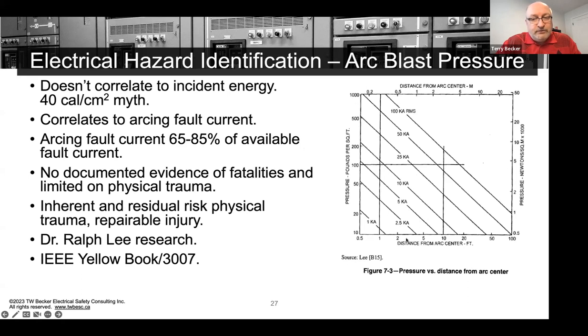This is a graph. We've got distance to the abnormal arcing fault, the arcing fault current, which will be lower than short circuit current, and then the theoretical pressure in pounds per square foot. So just a quick note on arc blast pressure. The good thing is we've now started to add content to 70E and Z462 so the user understands that blast pressure is not what it was previously communicated to be. It is not typically going to be very significant on standard low voltage power distribution and branch circuit electrical equipment.